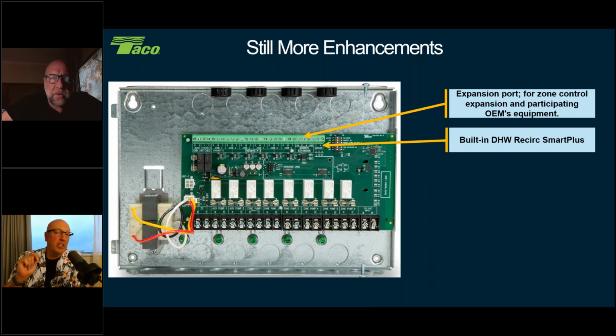For those of you that are doing domestic hot water recirc, we have added a terminal on here for the 10K sensor, and auxiliary pump 1 would be the relay to run your pump. For those of you that may be familiar, and if you're not, I believe in episode 9 of Taco After Dark, we're going to talk about the SmartPlus. So you have your SmartPlus technology built into this board already. If you already have a hydronic system installed in the house and you want to do domestic hot water recirc, you drop a sensor here on the terminals and you wire your circulator here rather than going to find an outlet for that circulator. So we built it into here already.